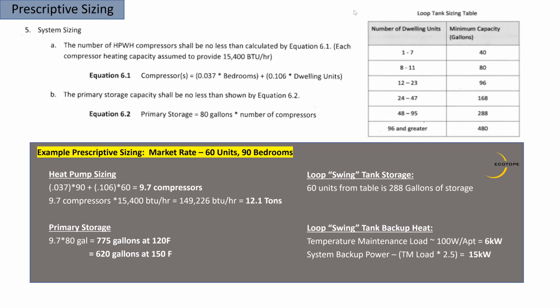And then the loop or swing tank usually has backup heat. This is an area that needs more research, but for the temperature maintenance loads right now, we've looked at about 8 or 10 buildings, and we know approximately what the losses are, and these are expressed in watts per apartment. We typically use around 100 watts per apartment for sizing. Then we do our redundancy in upsizing that coil, and a factor of 2.5 on that temperature maintenance will cover you for most of the hot water draw. The peaks might be impacted, but that's to allow you some hot water while any issues are addressed. Again, this will be refined in the next iteration of the sizer, but this is available now for folks to use to actually get designs rolling forward in central heat pump water heating.